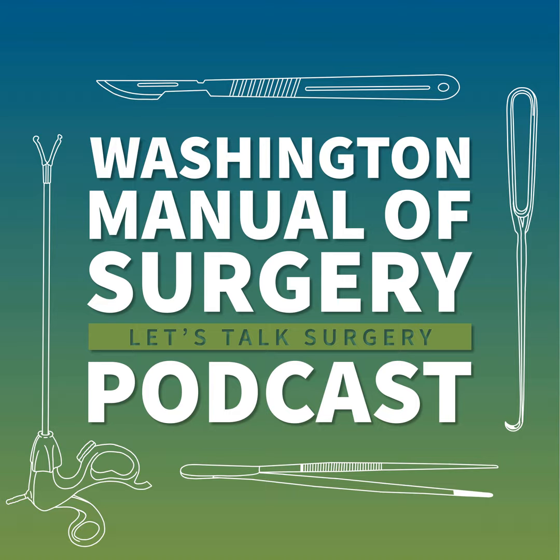The other alternative cautery that's also commonly used is what's known as bipolar. This is more frequently used in neurosurgery and head and neck procedures, but basically there's a single forceps that has two contact points, controlled by a pedal. The electricity travels between those two points on the forceps, so there's no need for a separate grounding pad, and that reduces thermal spread because the electricity is only traveling between the two points of the forceps.